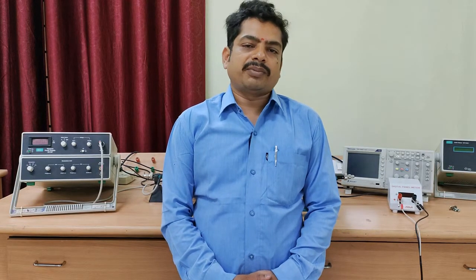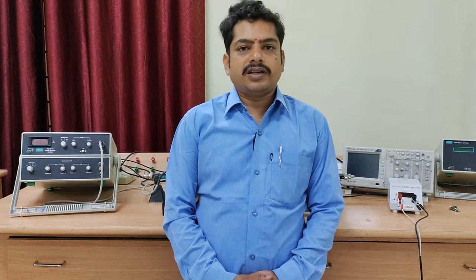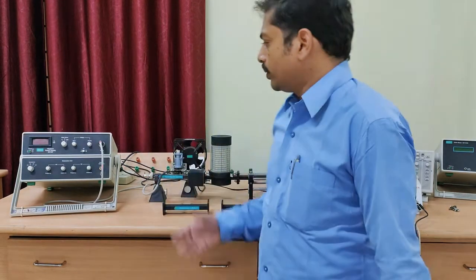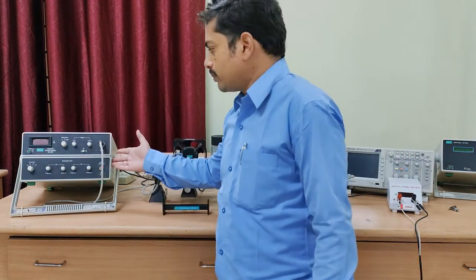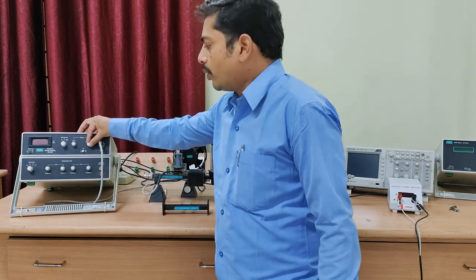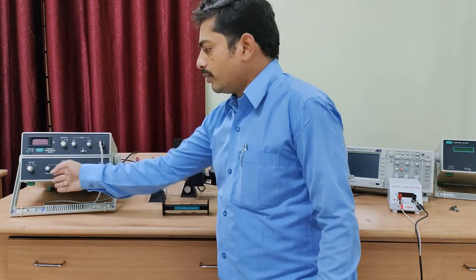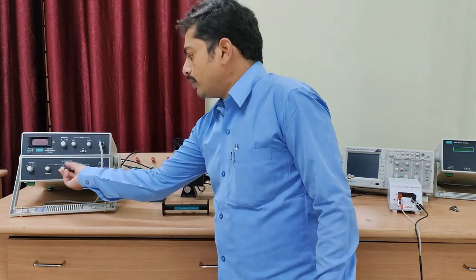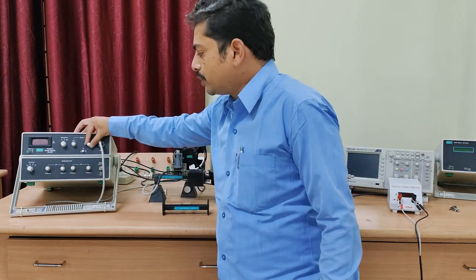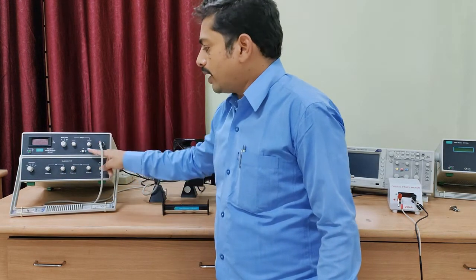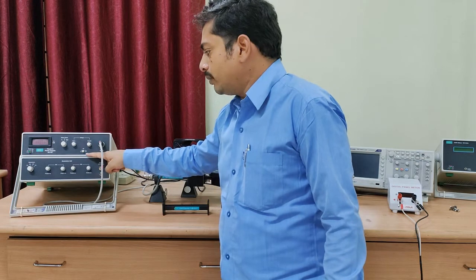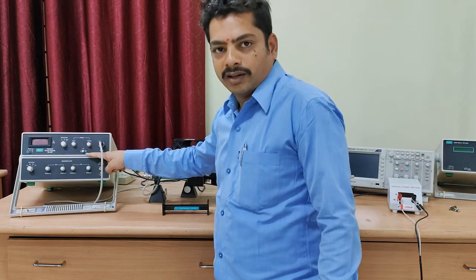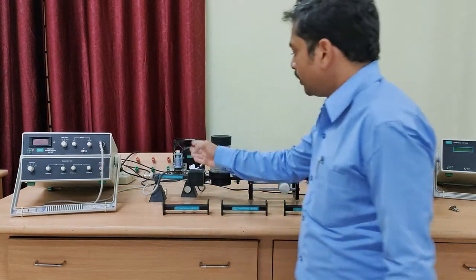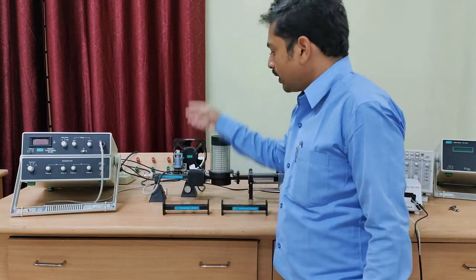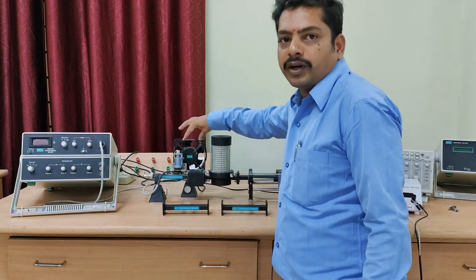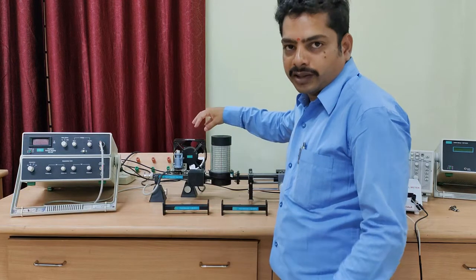Before starting any experiment, you have to check initial conditions. Now coming to the klystron power supply, except regulated voltage, all variable knobs should be in minimum position. Reflector voltage should be in max position. And always the HT push-pull button should be in off condition. Coming to the tube, klystron fan should be on for the entire experiment and after the experiment also.